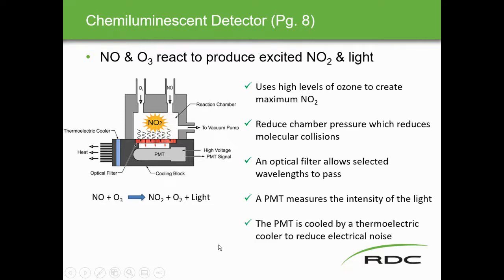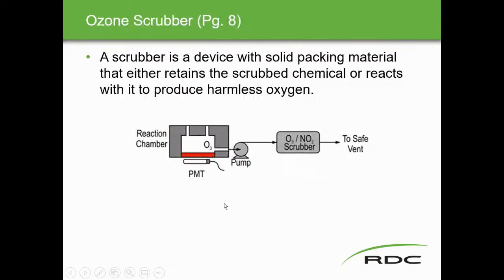NO2 and O3 are toxic and must be scrubbed before venting. A scrubber uses solid packing material that either retains chemicals or reacts with them to produce harmless oxygen. Surplus O3 is pumped out, scrubbed, and only safe oxygen is vented. The NO2 in the exhaust stream is also scrubbed.